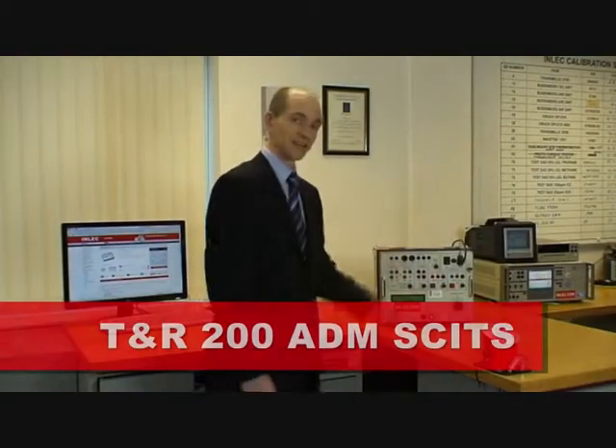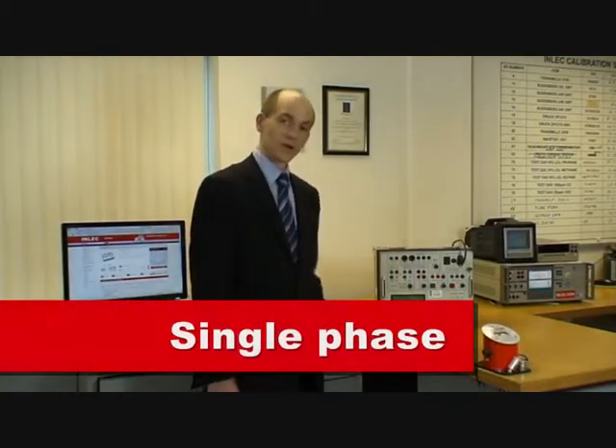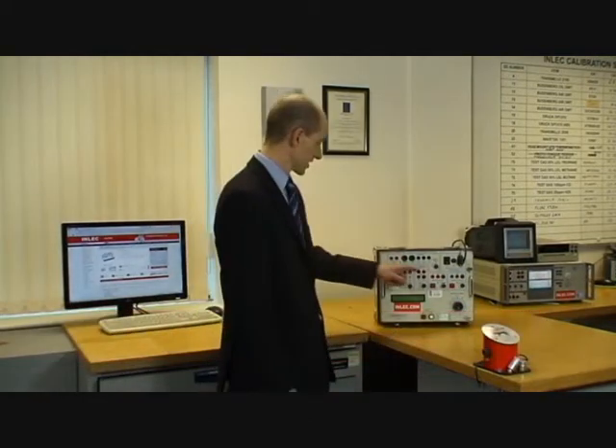Hello, I'm Ian Laid from T&R Test Equipment, and I'm here today to tell you about the 200ADM secondary injection set. It's a single phase injection set with an output current of up to 200 amps for short periods. It's also got an auxiliary AC voltage on it, so that you can put voltage as well as current on a relay.